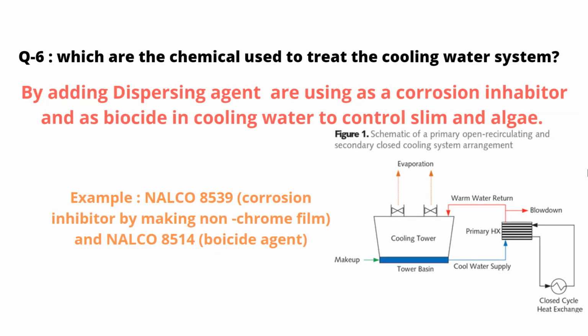Which are the chemicals used to treat the cooling water system? By adding a dispersing agent, or using a corrosion inhibitor and a biocide in cooling water to control slime and algae. Example, Nalco 8539 corrosion inhibitor, which makes a non-chrome film, and Nalco 8514 biocide agent.